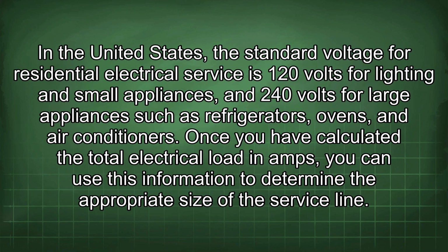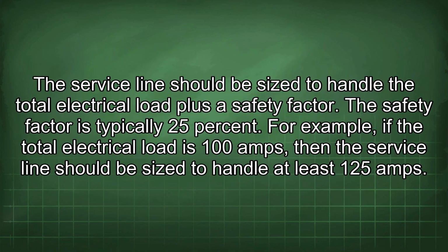In the United States, the standard voltage for residential electrical service is 120 volts for lighting and small appliances, and 240 volts for large appliances such as refrigerators, ovens, and air conditioners. Once you have calculated the total electrical load in amps, you can use this information to determine the appropriate size of the service line. The service line should be sized to handle the total electrical load plus a safety factor. The safety factor is typically 25%.